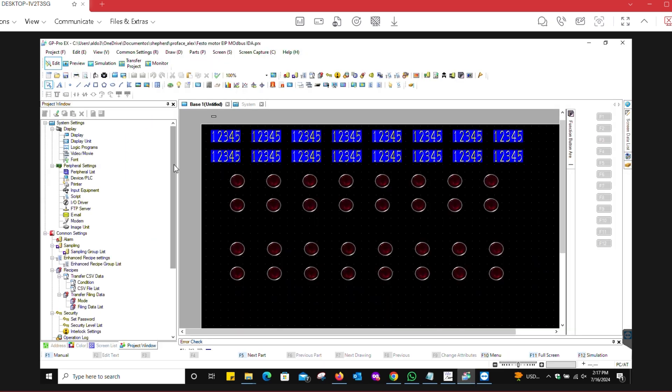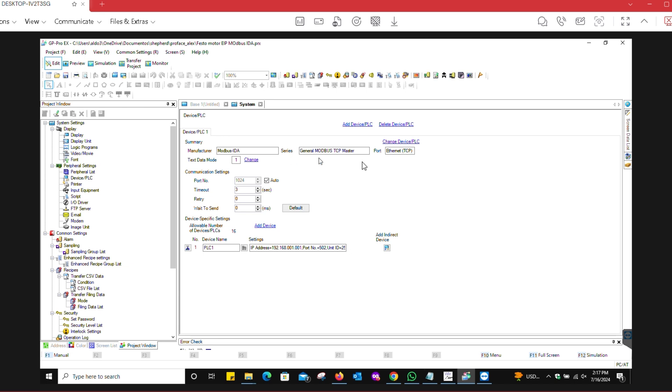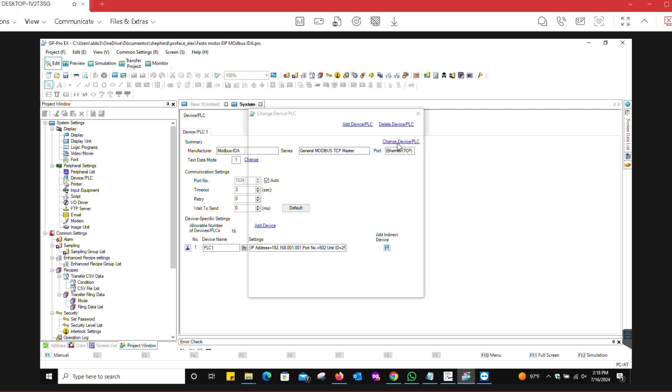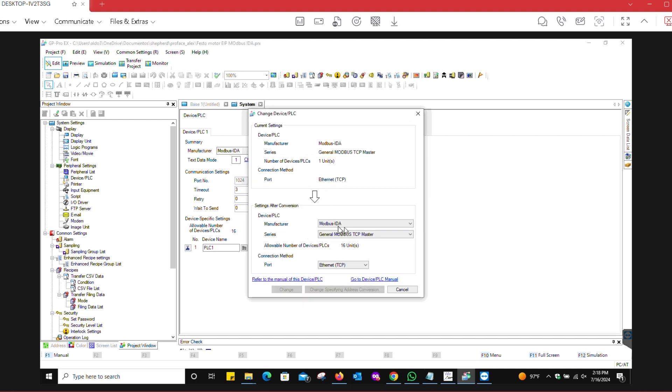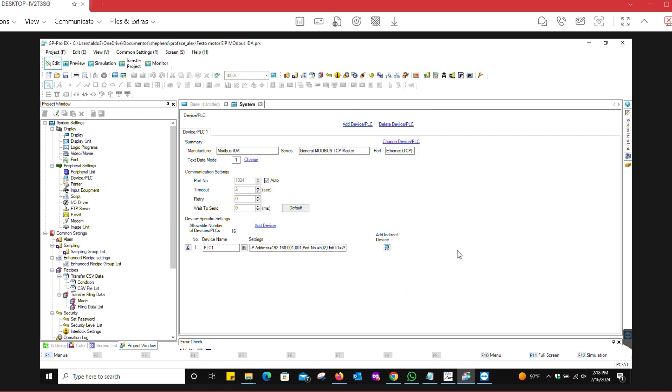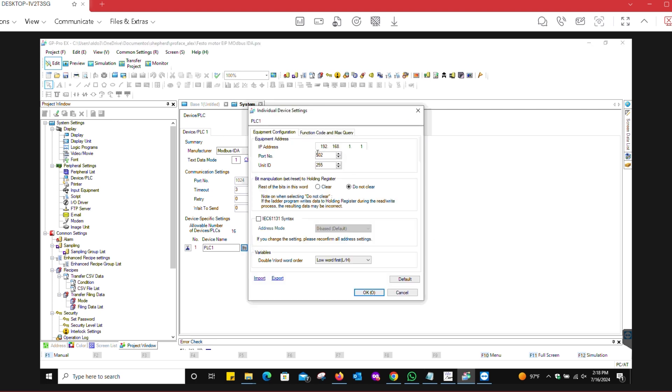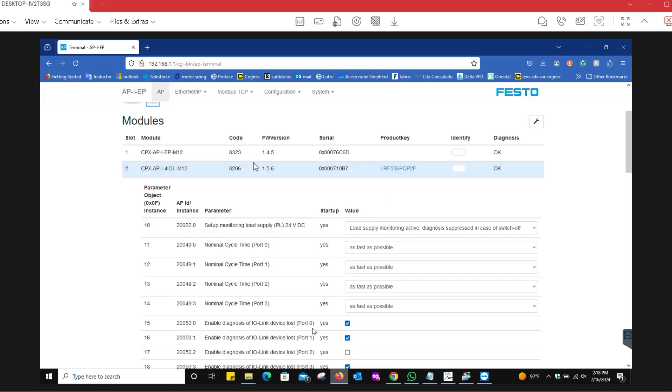Going to the software side of things, this is GP Pro EX for ProFace. The biggest thing to know here is that there's certain things that you got to account for. You're gonna go to Device PLC under Peripheral Settings, and in this case we're using Modbus IDA. You could also use some other versions, but in this case we're using Modbus IDA, General Modbus TCP Master, Ethernet TCP.